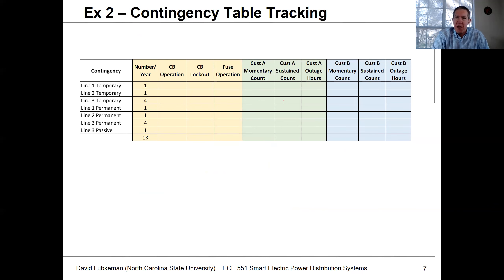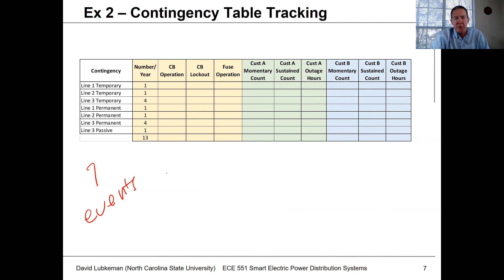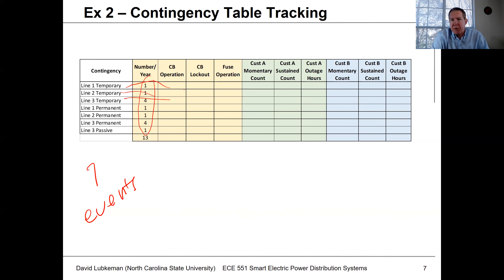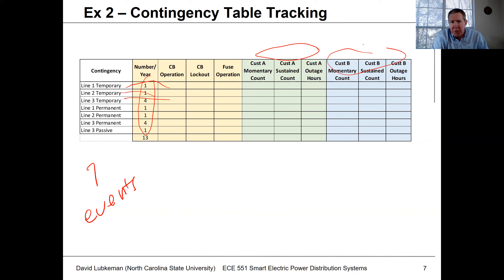I like putting all this information into a table to help with the bookkeeping. There are seven different types of events that could occur for these three line segments. For each event, I enter the number of occurrences per year and fill out the table regarding how many times the circuit breaker operates, whether it locks out, whether there's a fuse operation, and track the customer impact counts for customers A and B. For a practical circuit with maybe 500 customer locations, this has to be all computer code.